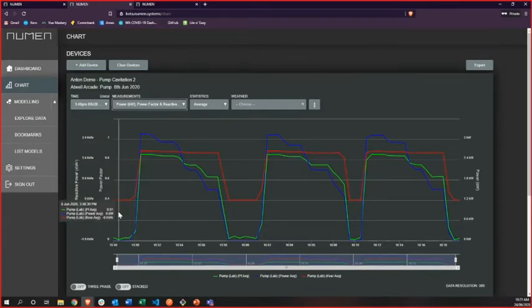Typically we run the pump with the valve open at 100%, then gradually close it down to 75%, then 50%, then 25%, which essentially creates a cavitating state for the pump. So the pump is in a cavitation state there, and then we switch the pump off again.